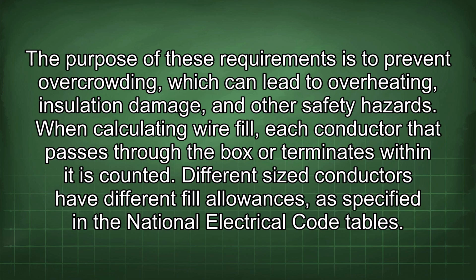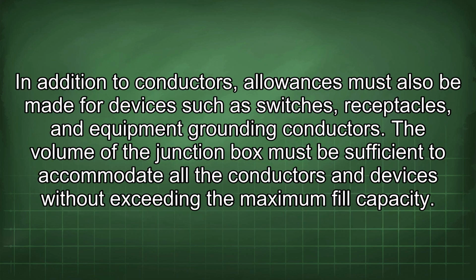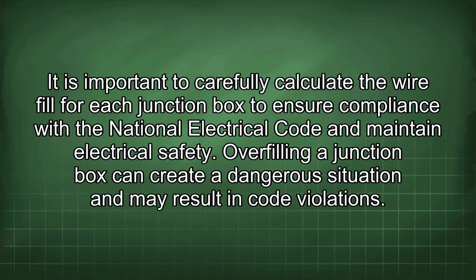When calculating wire fill, each conductor that passes through the box or terminates within it is counted. Different size conductors have different fill allowances, as specified in the National Electrical Code tables. In addition to conductors, allowances must also be made for devices such as switches, receptacles, and equipment grounding conductors. The volume of the junction box must be sufficient to accommodate all the conductors and devices without exceeding the maximum fill capacity. It is important to carefully calculate the wire fill for each junction box to ensure compliance with the National Electrical Code and maintain electrical safety. Overfilling a junction box can create a dangerous situation and may result in code violations.